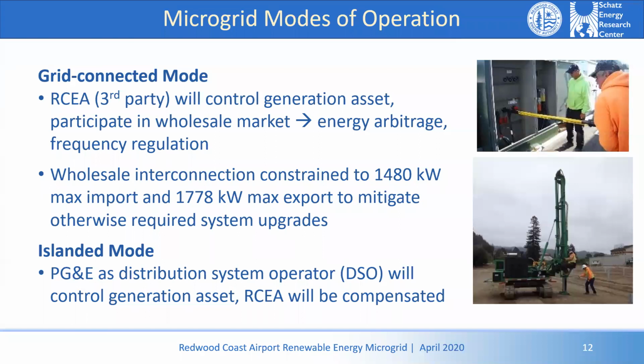So the microgrid that Matthew just described, the different components, there basically are two modes for a microgrid, and that's really what defines a microgrid: DERs that have the ability to not only run in parallel with the grid, but also to run in island mode, to isolate themselves from the bulk grid and form a microgrid. So those are the two modes of operation. And in this innovative partnership between RCEA and PG&E, there is a division of ownership and responsibilities on this system. And I'll go through some of that in terms of the actual equipment, not piece by piece, but give you a sense of the division there.